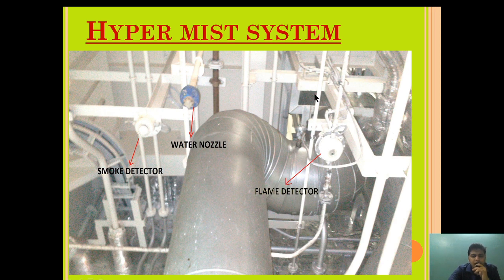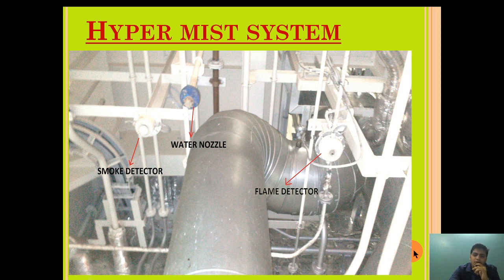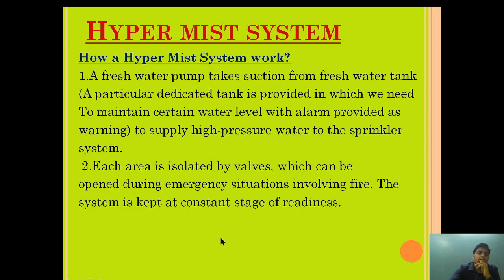In this diagram, above the boiler you can see the flame detector, the Hypermist nozzle, and the smoke detector. Suppose a flame erupts, generating smoke — the smoke detector will activate, and the flame having a certain frequency range will be detected by the flame detector. Once both activate, Hypermist will be injected through the water nozzle and the flame will be extinguished.